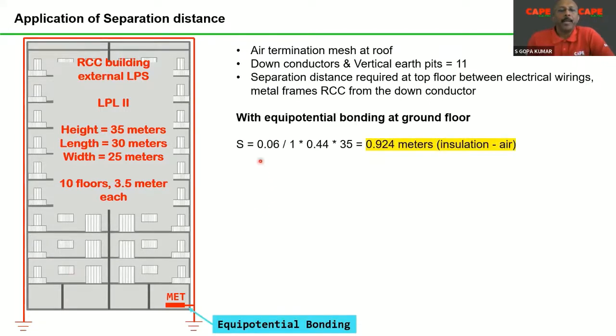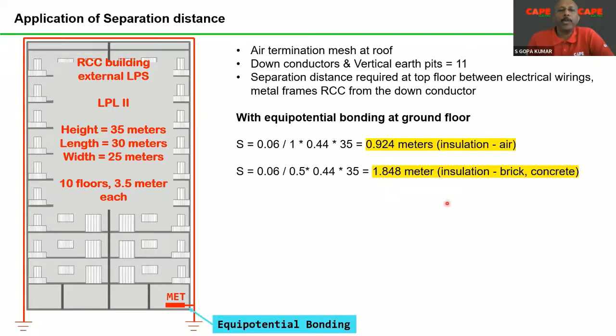If we take the values from the constants, S equals Ki divided by Km, into Kc, into L. L is the distance from the top of the building down to the equipotential bonding, which is the height of the building in this particular case. If we calculate the separation distance required in this kind of building, a 10 floor building, it is about 0.924 meters. Almost 1 meter of insulation is required in air, and almost 2 meters of insulation is required in the case of brick or concrete.